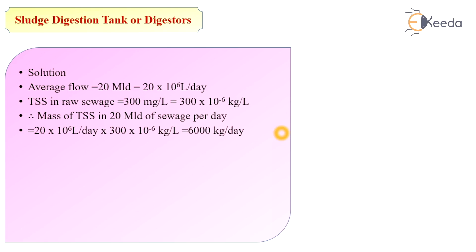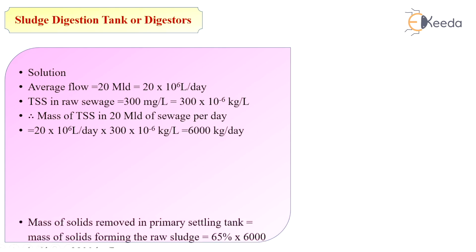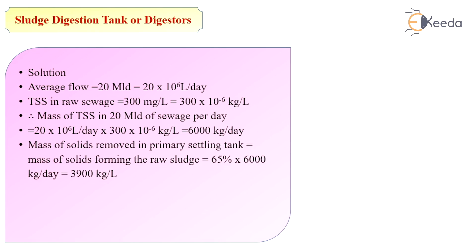The mass of total suspended solids equals 20 × 10⁶ × 300 × 10⁻⁶ kg per liter, which equals 6000 kg per day. The mass of solids removed in the primary settling tank equals 65% of 6000, which equals 3900 kg per day. In primary sedimentation we remove 65% of mass solids, so we multiply 65/100 × 6000 to get 3900 kg per day.